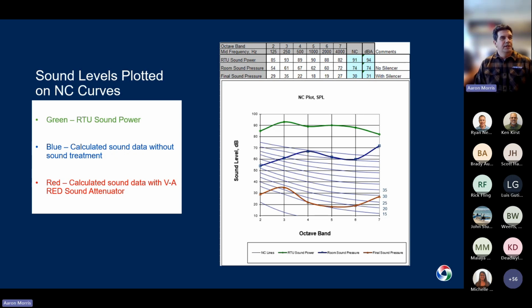So handy little tool. In this case, we plotted the sound power straight from the rooftop unit in green, which is clearly way too loud for the NC30. And then the blue would be if we did not use our silencer. It just, in the short amount of ductwork we had to get to this space, is still going to be way too loud. So then in red, we plotted it with the Vibro-Acoustics sound attenuator. And you can see that each octave band comes in below that NC30 contour line, meeting the requirement for this project. And you can see in the final sound pressure here, we resulted in the NC30 and we had a dBA of 31.